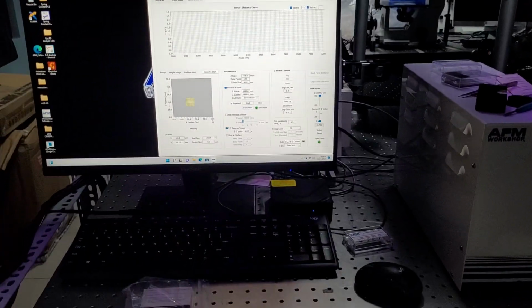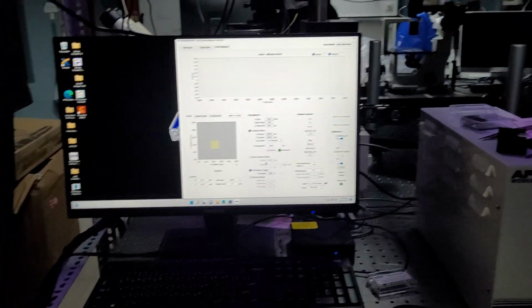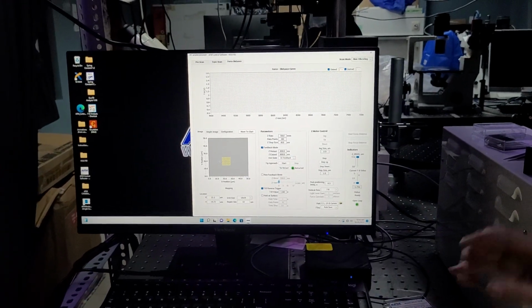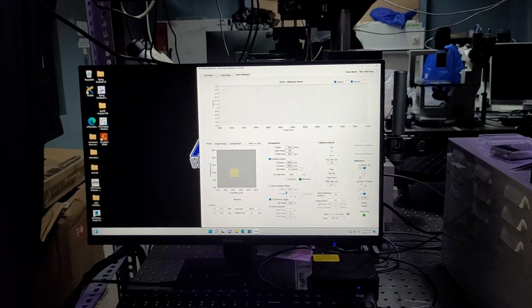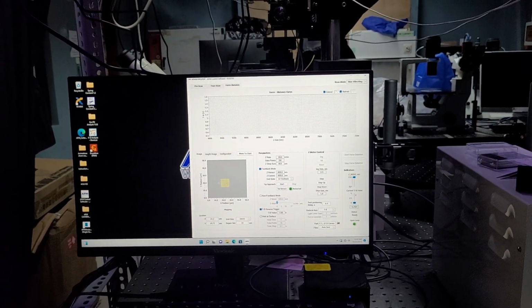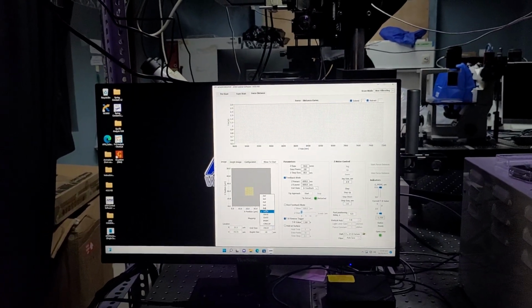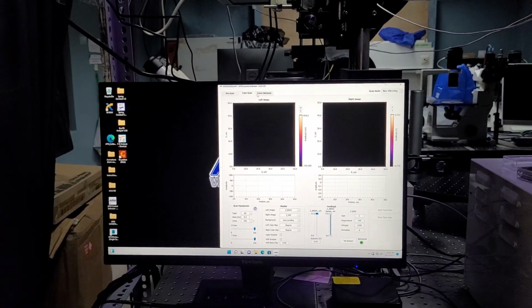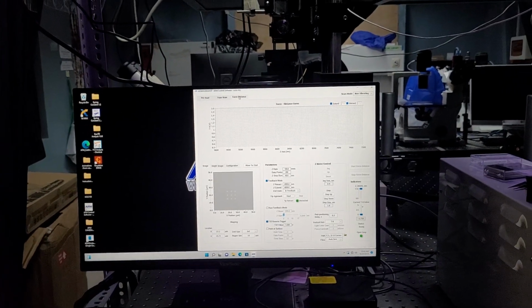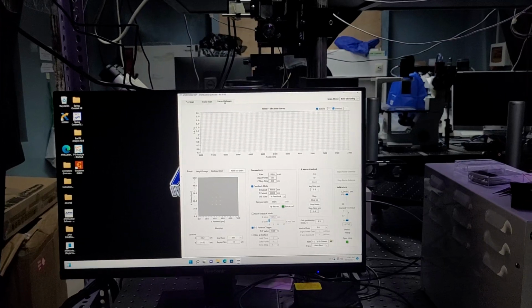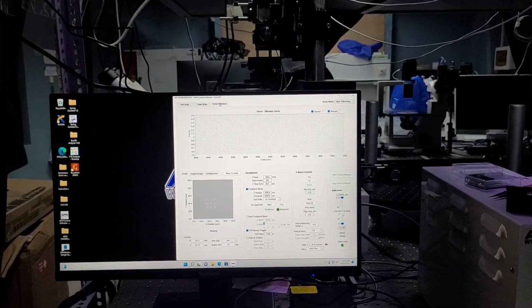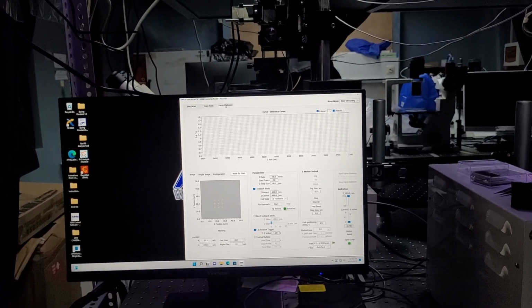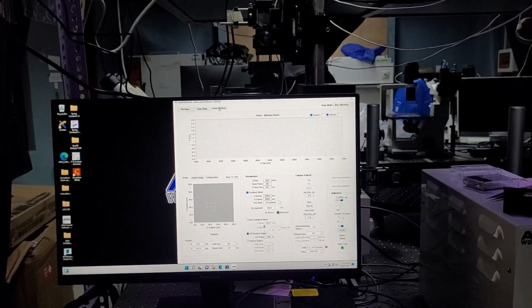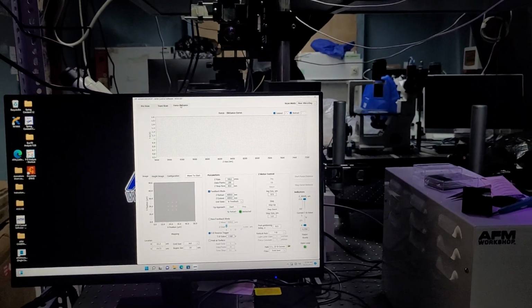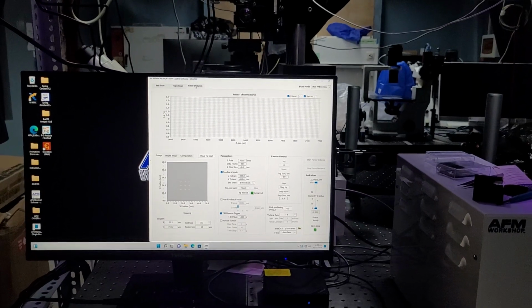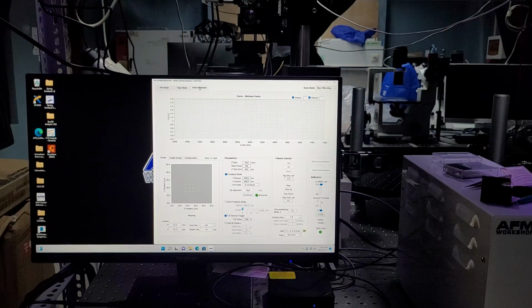So for example, if you had a sample that had a lot of cells, and you wanted to look at the differences between the cells or between the cells and the substrate, then you could set up a grid and take force distance measurements on those cells and on that substrate to be able to analyze it from there. This is not something that we will cover in the training necessarily. This is something that I would recommend you delve into once you've gotten better at using the AFM. Partially because with the force distance we include 2 force distance enabled probes, and so I don't want to break one showing you guys, because typically once you use a probe for force distance, it's no longer good. Typically you're putting a lot of force onto that cantilever, and eventually it will shear.